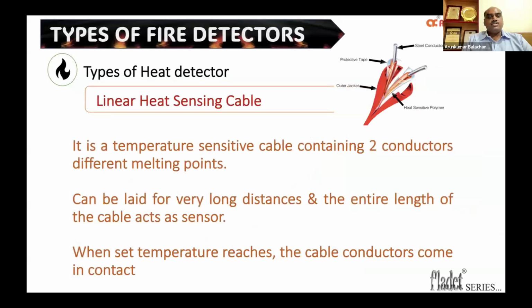We'll move on to the next detector, which is the linear heat sensing cable. The linear heat sensing cable, or the LHS cable, has two conductors which will fuse together when the set temperature is achieved. For example, if the set temperature is 88 degrees, and 88 degrees is reached at any point of this LHS cable, the conductors will fuse together to give an alarm signal.